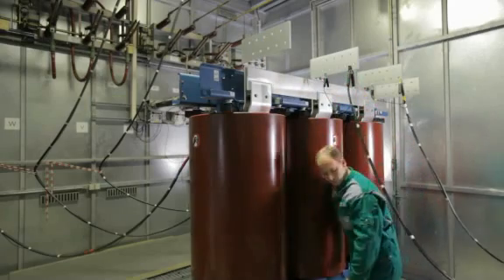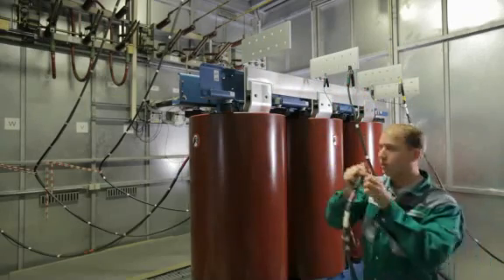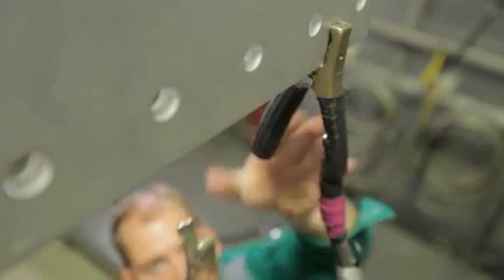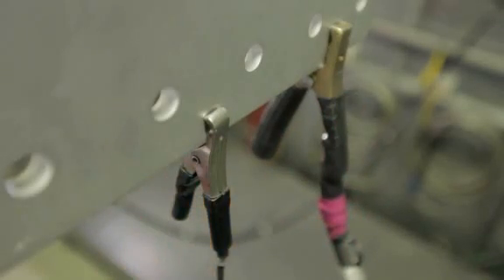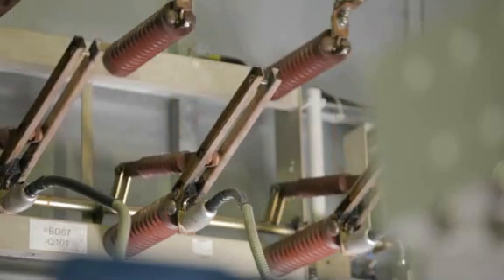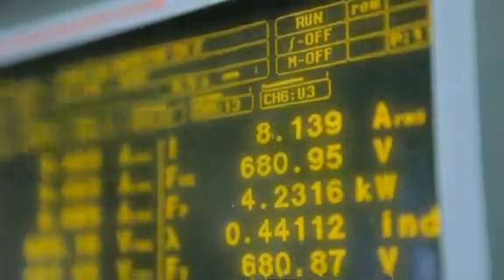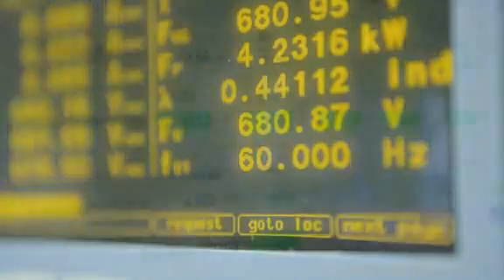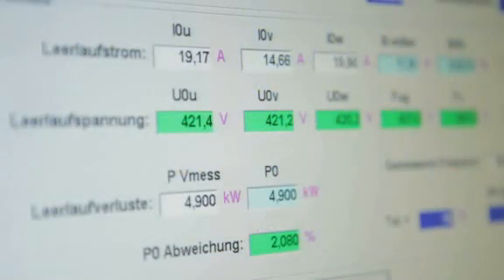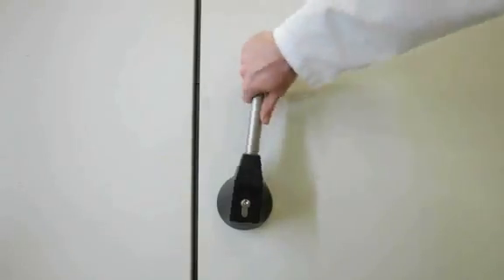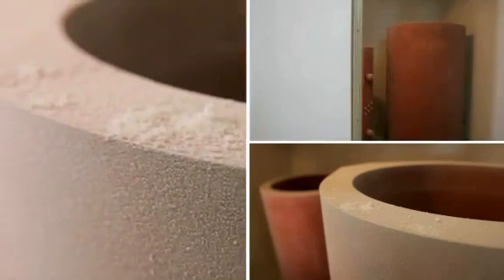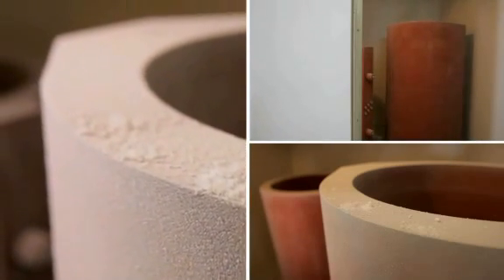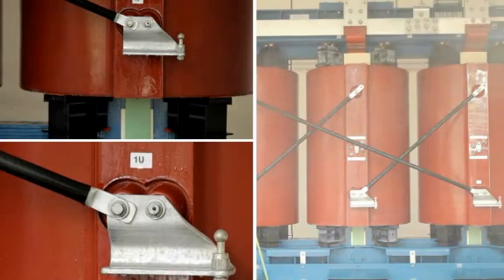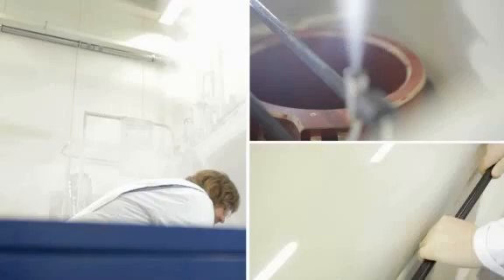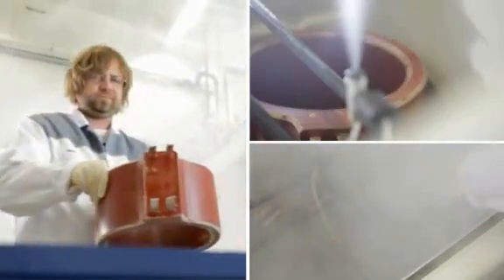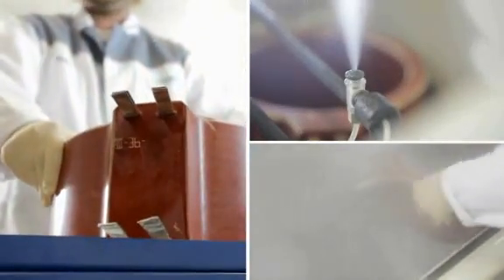We conduct nearly all type testing in our very own test bay, whether for lightning impulse tests or measuring noise and heating levels. Every single transformer is tested with up to twice the rated voltage to verify it is free from partial discharges. And just about every time, all readings show the green light. Yet our engineers are always coming up with new tests. Temperature shocks from -25 up to +140 degrees Celsius, a voltage test in heavily salty air, or a tropical test at 50 degrees Celsius and air humidity of 90%.